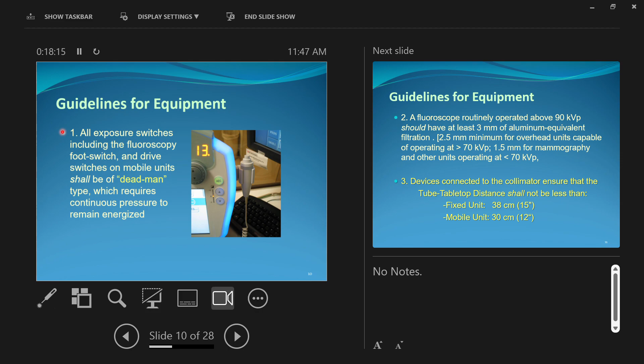In x-ray terms, our exposure button's a dead man's switch, which means if we set something like a 1 second exposure, we've got to press that button down for that entire time, okay? If you set a 1 second exposure, but let up before 1 second passes, the exposure will terminate before the timer runs out. Once you hold it for the full exposure time, any time holding it after that, the exposure has shut itself off. You have to hold the button for the minimum amount of time the exposure happens. If you let up before that, exposure stops. Dead man's switch.